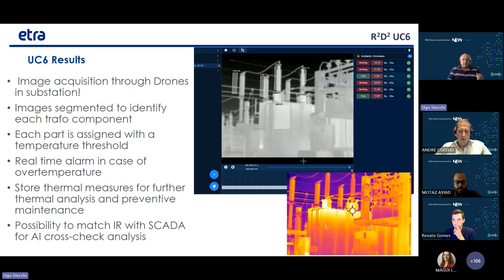Argos is able to identify the different sections and components within the transformer, setting different temperature thresholds and triggering an alarm in case of over temperature in each section. It is also possible within Argos to include measurements from SCADA, in order to perform cross-check analysis, matching temperature analysis from infrared images acquired via drones with real-time information from SCADA.